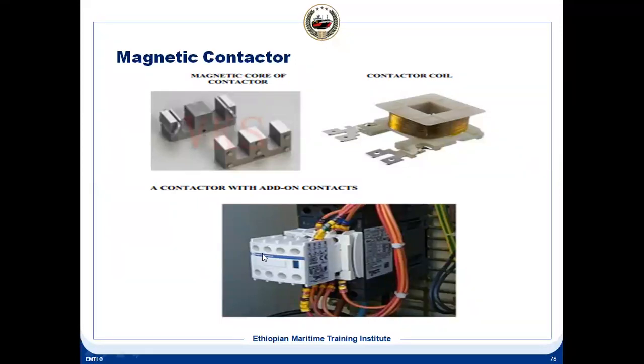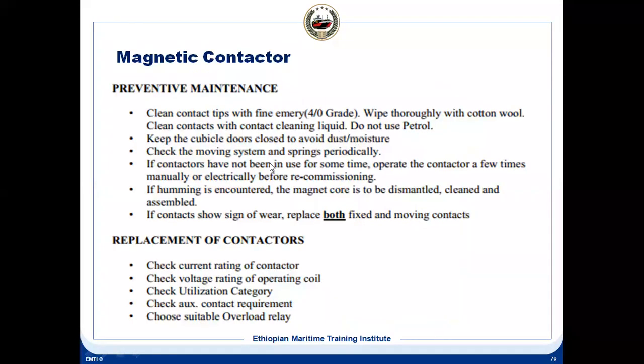This white one is a magnetic contactor. This is the coil which is inside. When you give a supply to this coil, it gets energized and makes a magnet and pulls the contact. So what is the general maintenance you carry out on a magnetic contactor? You can see the preventive maintenance, also a few replacements of contactors. These are the general maintenance you carry out on a starter contactor.